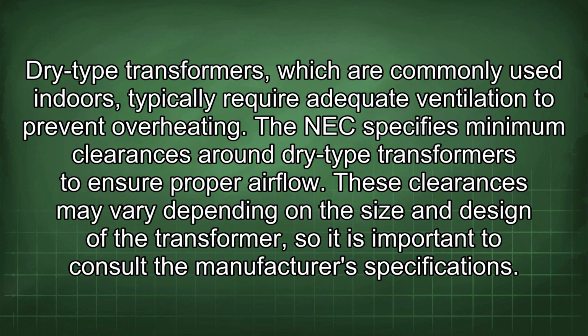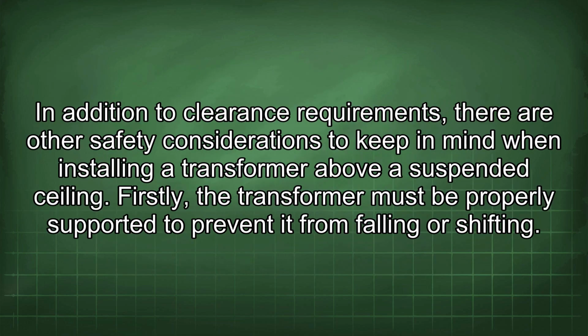Dry-type transformers, which are commonly used indoors, typically require adequate ventilation to prevent overheating. The NEC specifies minimum clearances around dry-type transformers to ensure proper airflow. These clearances may vary depending on the size and design of the transformer, so it is important to consult the manufacturer's specifications.